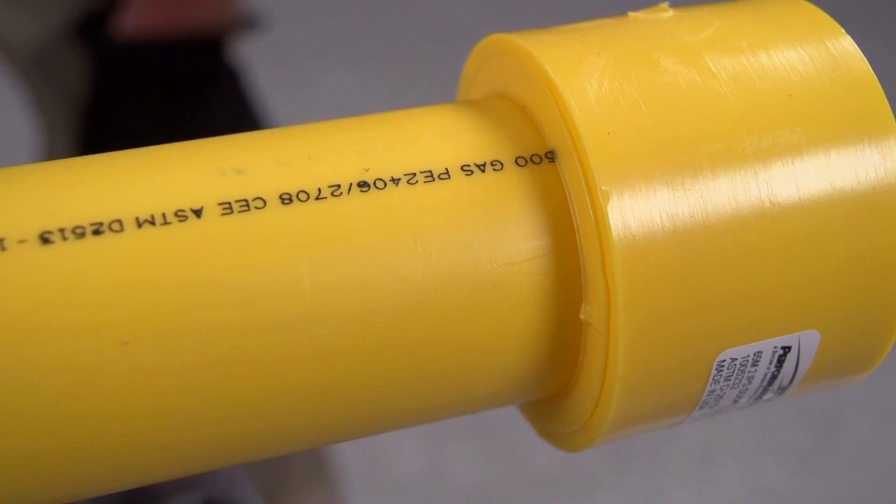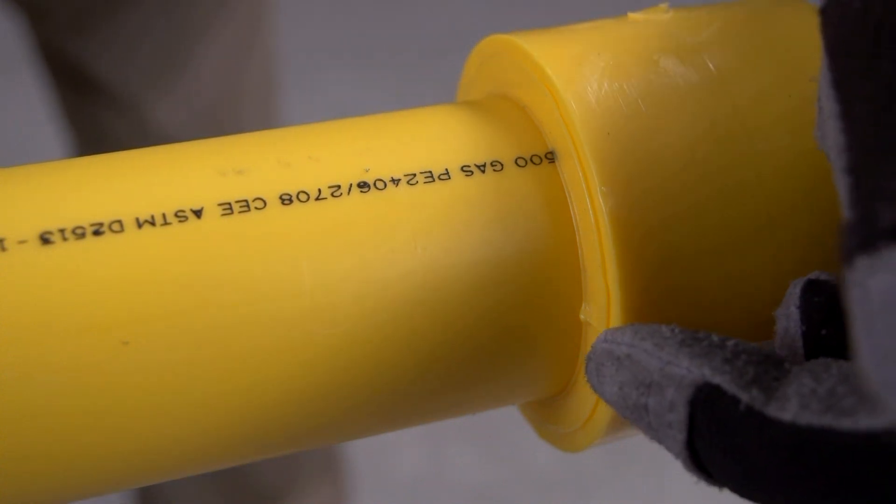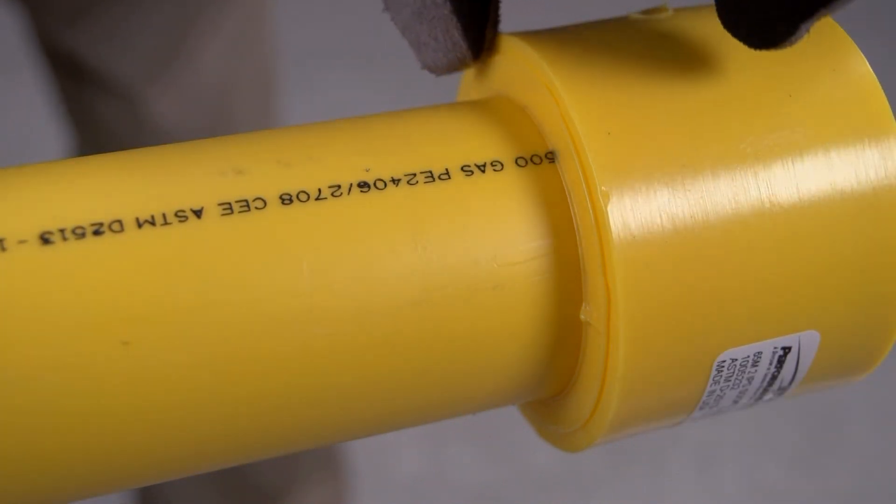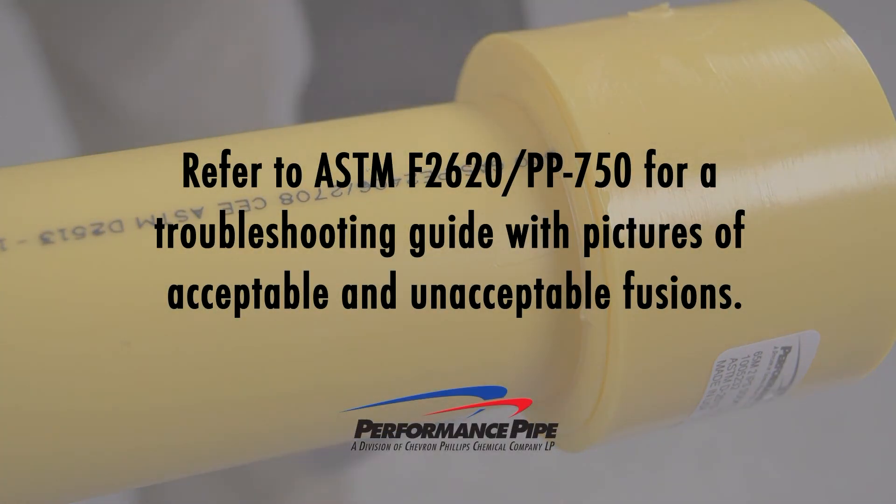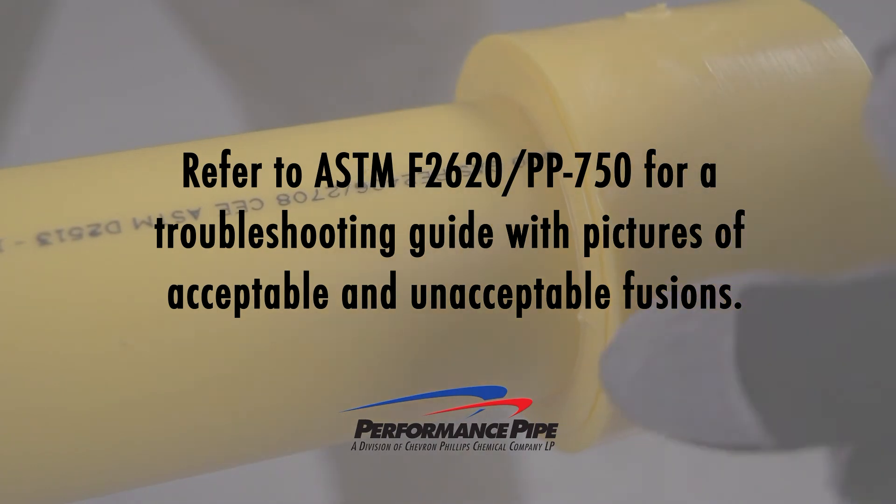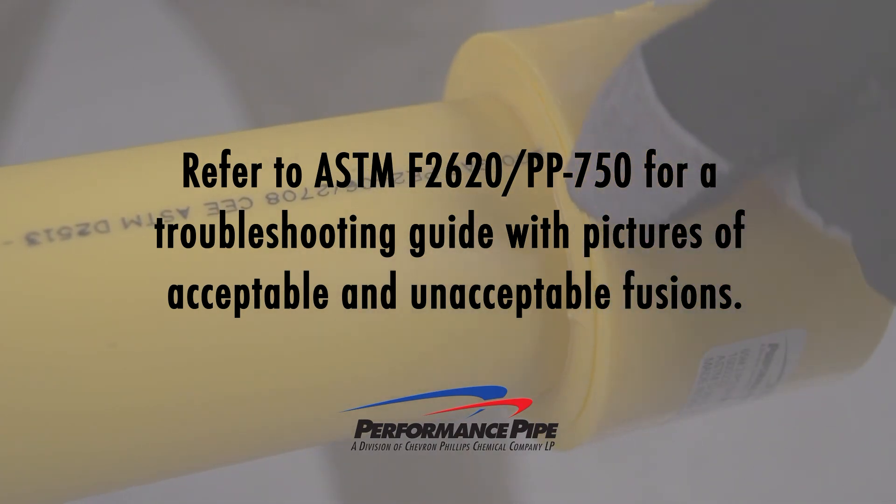Inspect the end of the socket fitting at the pipe. There should be a clear impression of the cold ring clamp onto the melted surface at the end of the fitting with no visible gaps or voids around the pipe and socket melt bead. The pipe and fitting should be aligned straight with each other. Refer to ASTM F2620 or Performance Pipe Bulletin 750 for a troubleshooting guide with pictures of acceptable and unacceptable fusions.